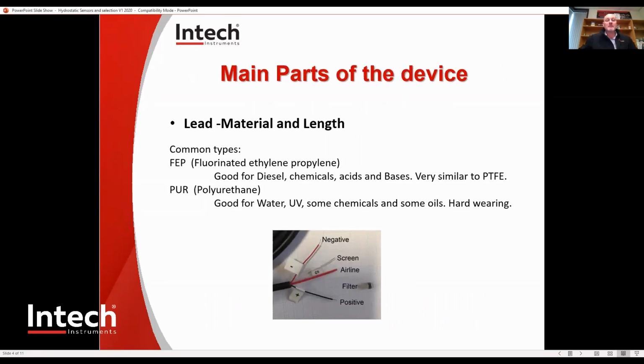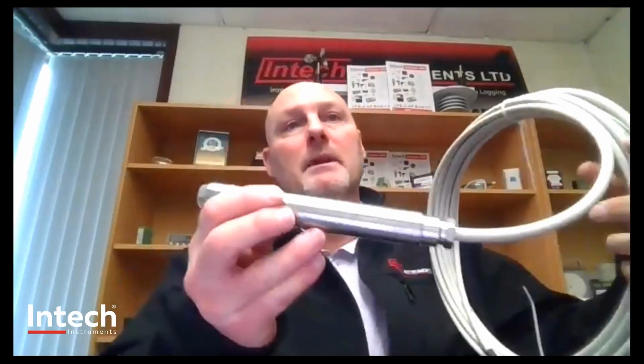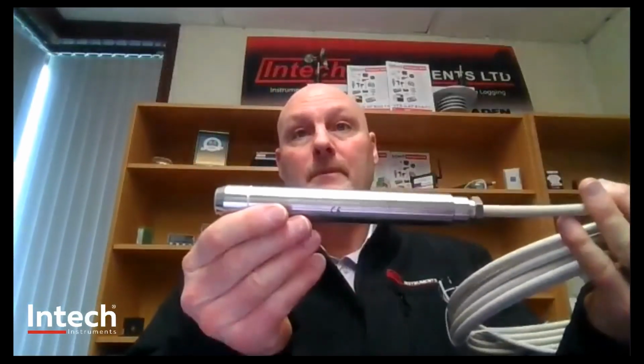Now we'll go into the main parts of the device, and here's one here. We have one of our level transducers from Jumo. This is our 404392, and typically the main parts are the lead. In this particular instance, it is a polyurethane lead. We have the main body of the transducer. We have the diaphragm, which is, as you can see, protected under a special cover right here, and any threads that may be required for the tip. I'll now break that down into a few other helpful bits and pieces.